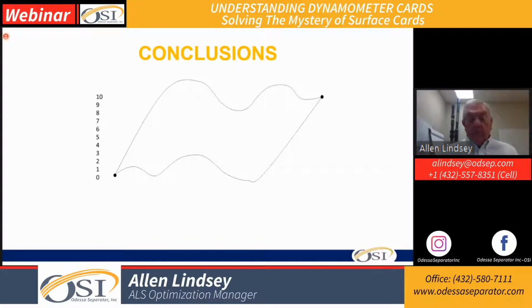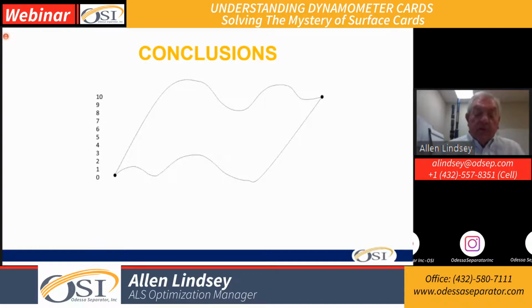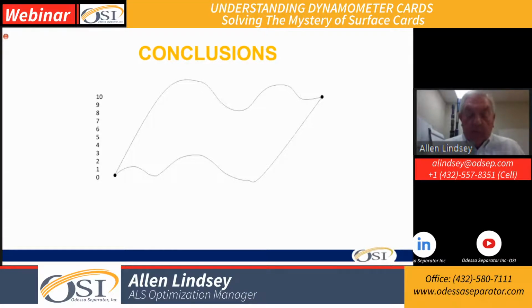Combining these two figures produces a very good approximation of a surface dynamometer card for a properly operating well with a full pump barrel. In conclusion, the shape of a surface dynamometer card is a result of rod stretch in relation to pumping speed. In the next dynamometer webinar, we will discuss how operating problems affect the shape of both surface and downhole dynamometer cards and the correlation between the two.